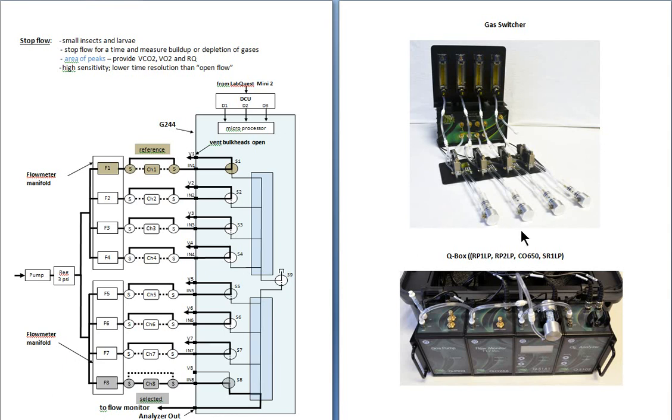The modules fit into a tray. They're plumbed. The gas is dried before it is analyzed by the gas analyzers. The calibration is performed on the gas analyzers after the tray has been placed back into the weatherproof suitcase.